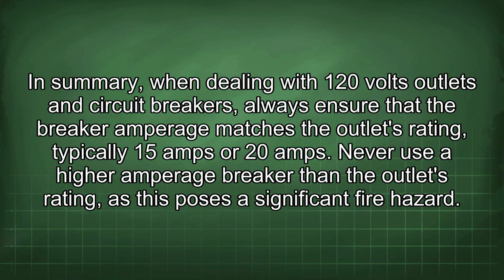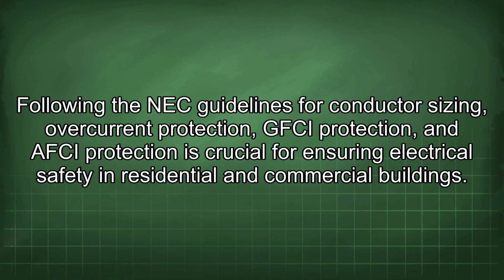In summary, when dealing with 120 volts outlets and circuit breakers, always ensure that the breaker amperage matches the outlet's rating, typically 15 amps or 20 amps. Never use a higher amperage breaker than the outlet's rating, as this poses a significant fire hazard. Following the NEC guidelines for conductor sizing, overcurrent protection, GFCI protection, and AFCI protection is crucial for ensuring electrical safety in residential and commercial buildings.